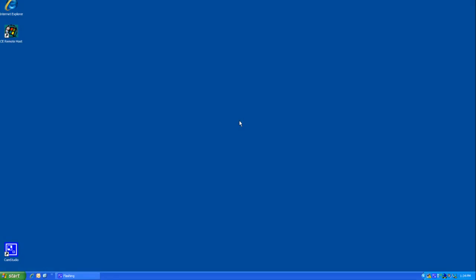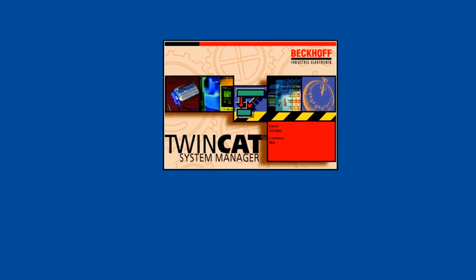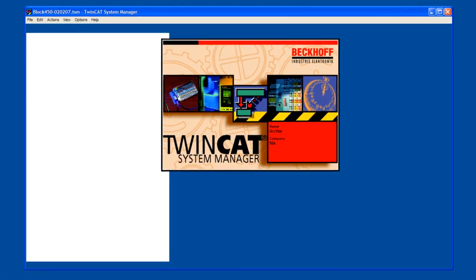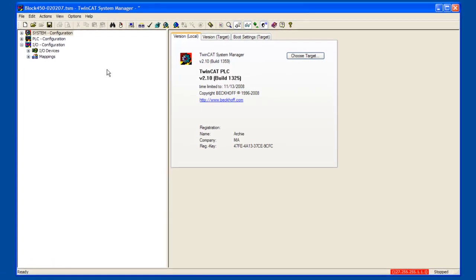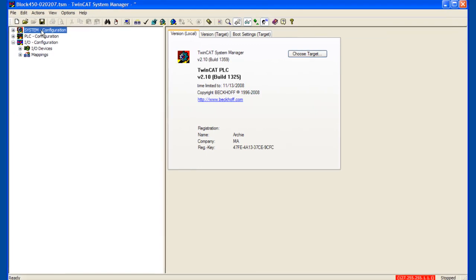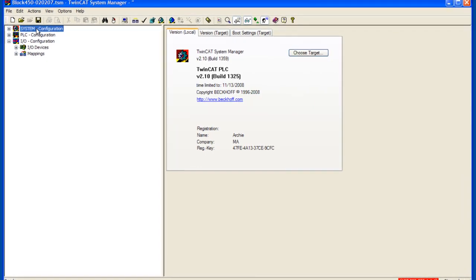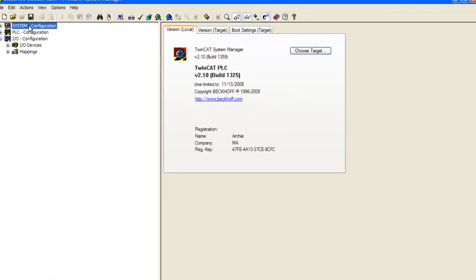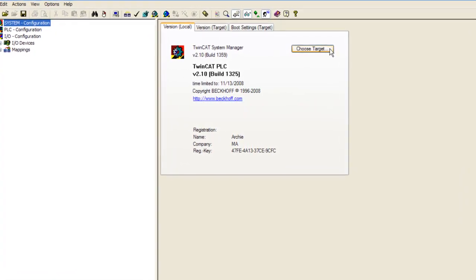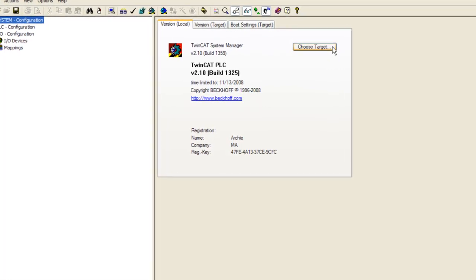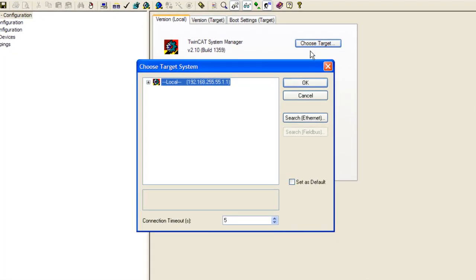Let's now configure TwinCAT to establish our communications between the development environment and the runtime on the CX processor. We are going to do this by going down to the TwinCAT icon down by the clock and left click and select system manager. Now once system manager opens up, go to the upper left where it says system configuration and click once to highlight that. And to the right you should see a choose target button. Left click the choose target button and you will get a choose target system window.